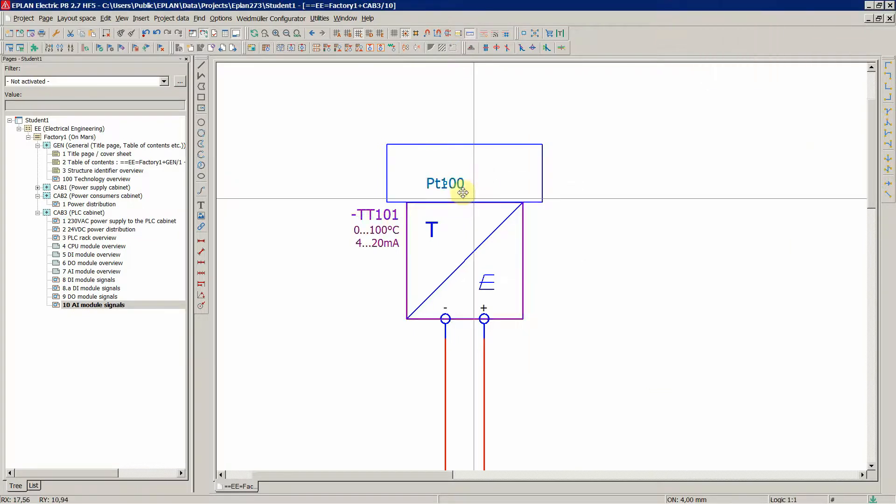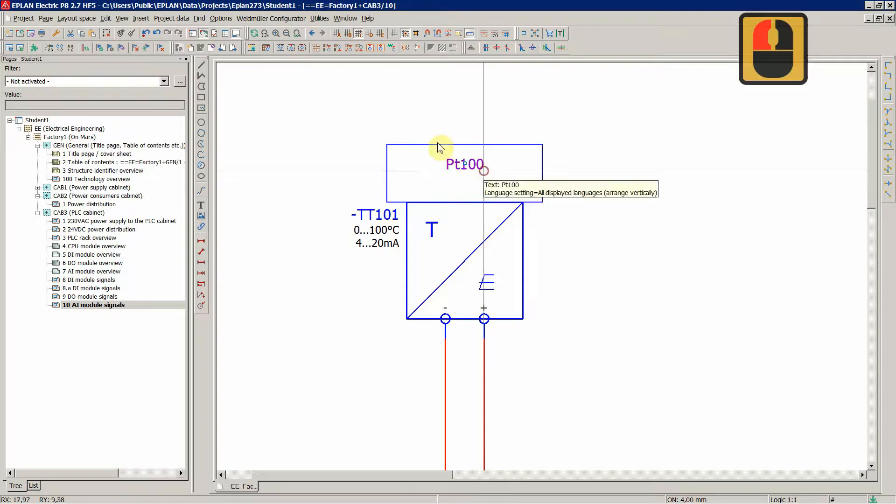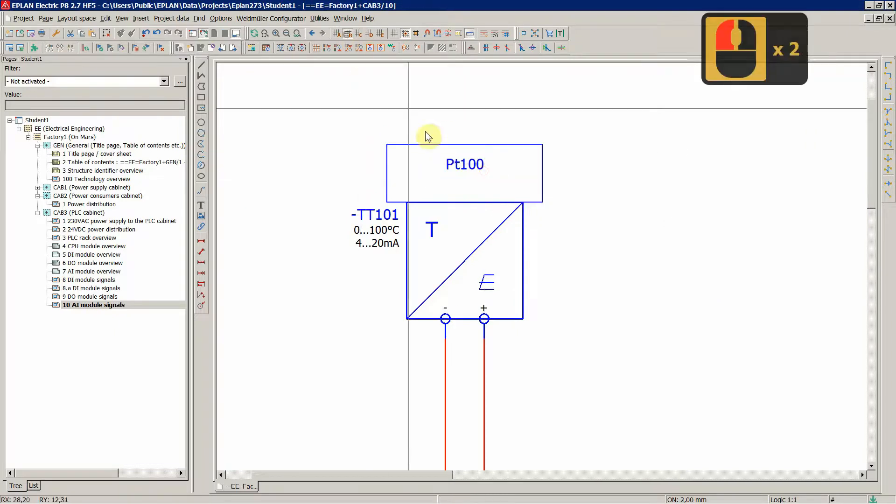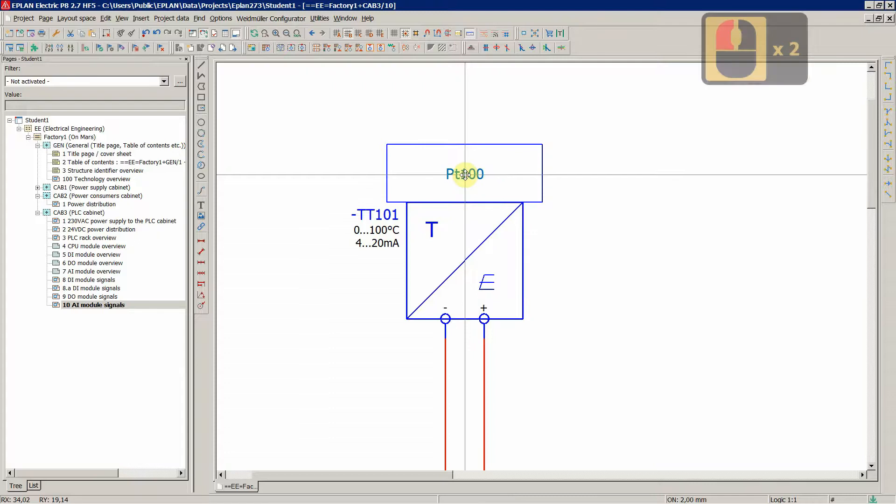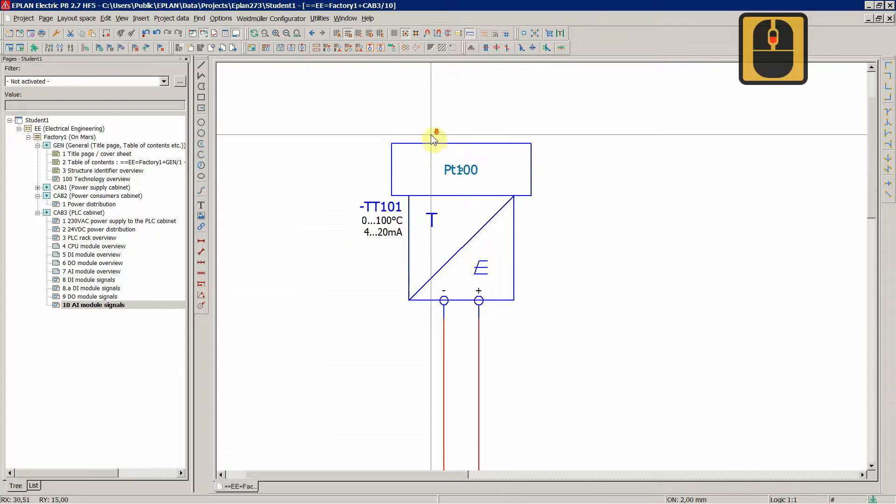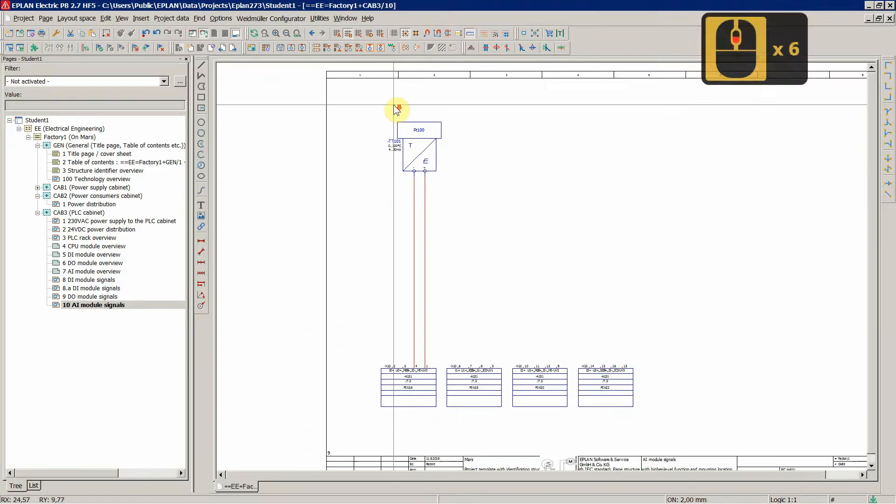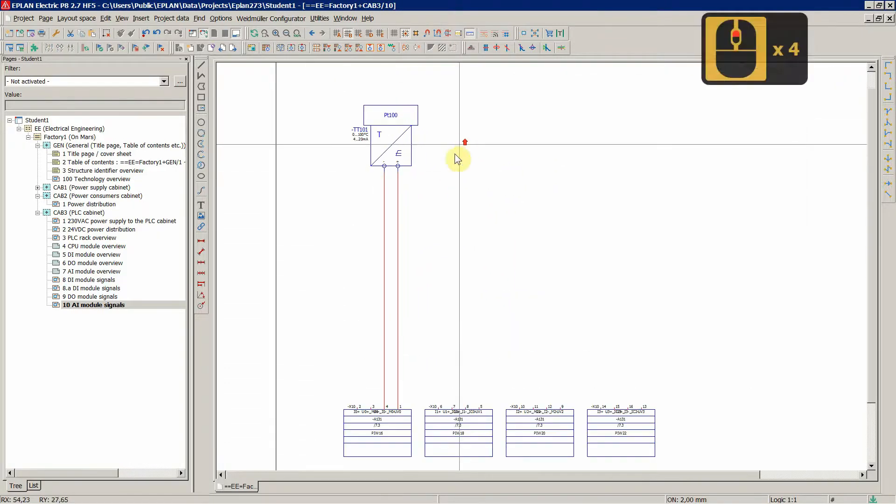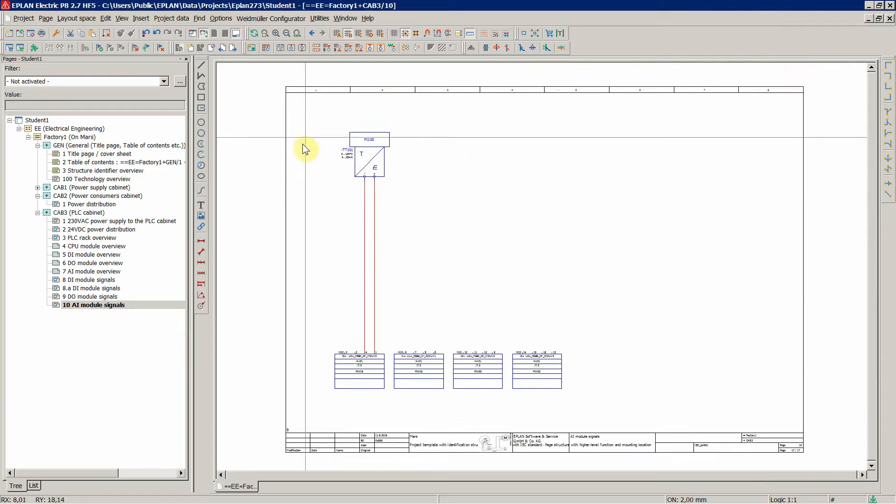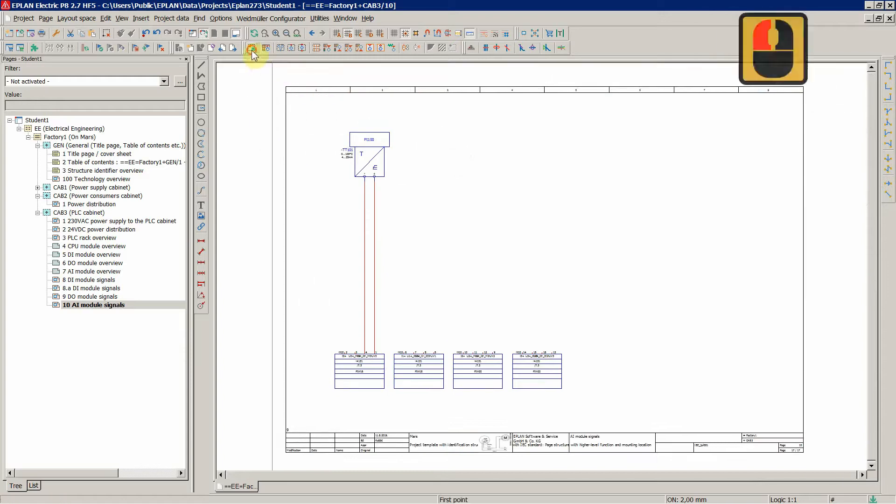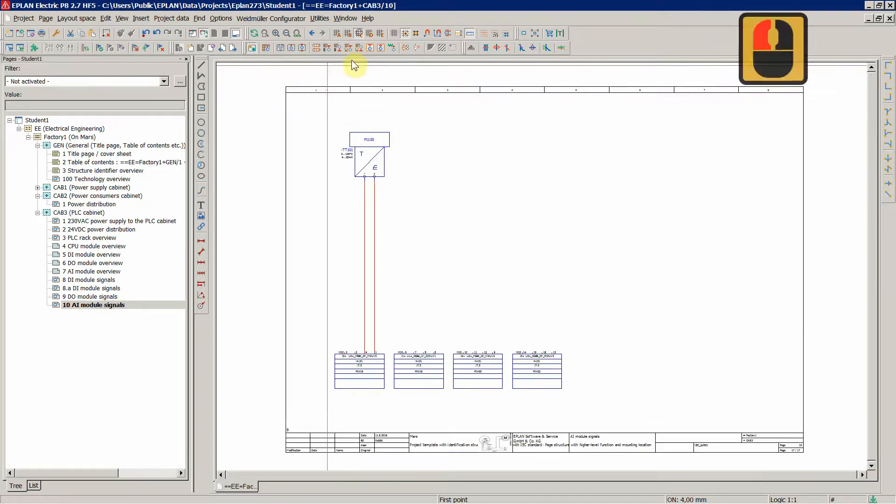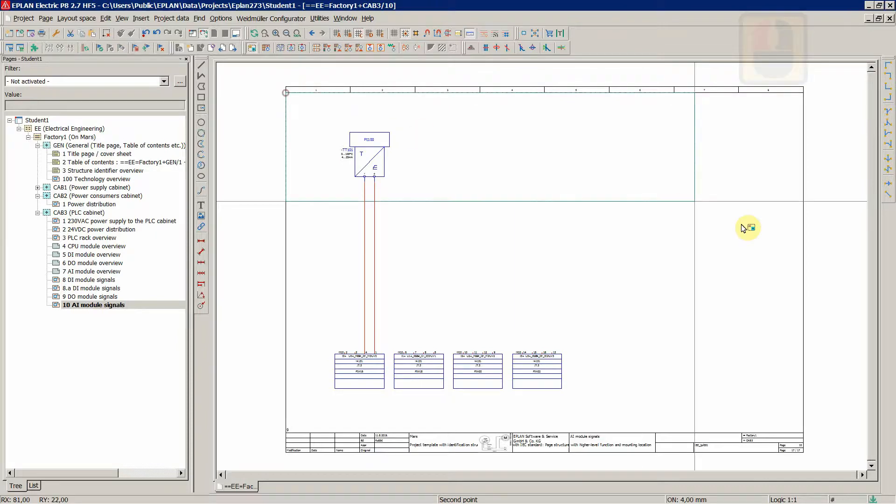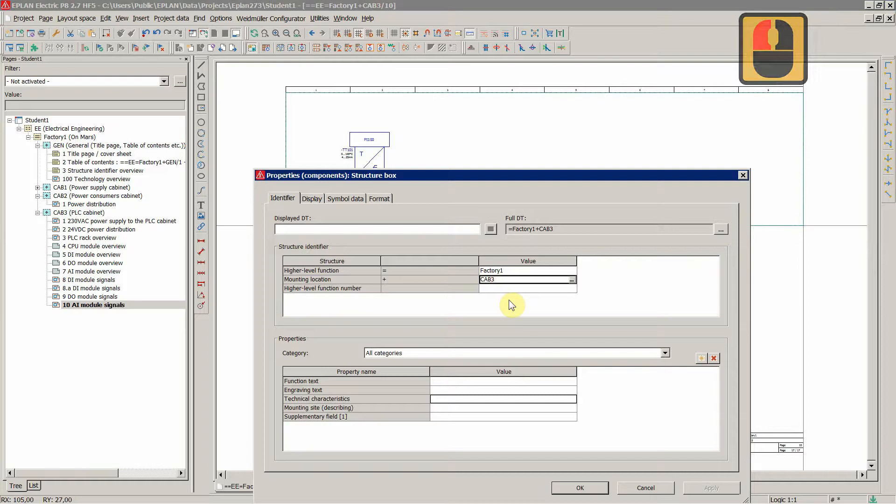This is a so-called instrument loop. So in the oil and gas industry you normally draw loops in E-PLAN horizontally. So on the left side of your plot frame it will represent your instrument transmitter, here on the far right side of your plot frame your PLC input.